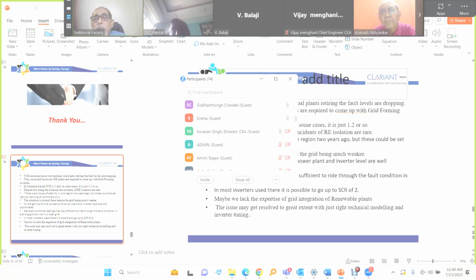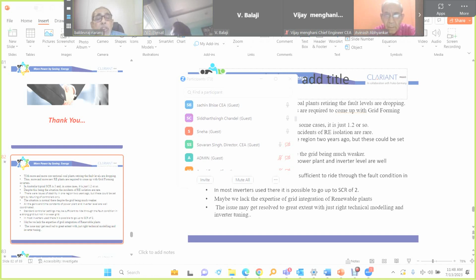So what I wanted is, the people who have made these things mandatory must have some genuine reasons. I wanted to hear from them the reasons why they have done it. What is the mandatory rule? It is that reactive power compensation has to be done through STATCOM, 100% dynamic. For the places you are talking about, it doesn't matter; switched capacitor banks are good enough to do that, but at those locations the problems are there. What I was saying is, even if we have STATCOM, even if we have fully dynamic, because of the grid strength we may not be able to cope up with the situation. That was my question, and I am not able to get any answer for that.